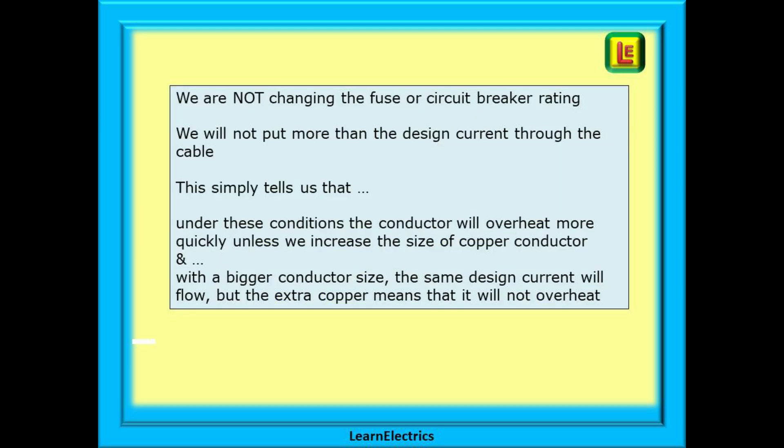You must understand that we are not changing the fuse or circuit breaker rating. And we will not put more than the design current through the cable. It simply tells us that, under certain conditions, the conductor will overheat more quickly unless we increase the size of copper conductor. And with the bigger conductor size, the same design current will flow, but the extra copper means that it will not overheat. It is still the same 4kW load, the same 17.3 amps of design current, and the same fuse rating of 20 amps. We are just going to use bigger cable, and these calculations tell us how big the cable should be.